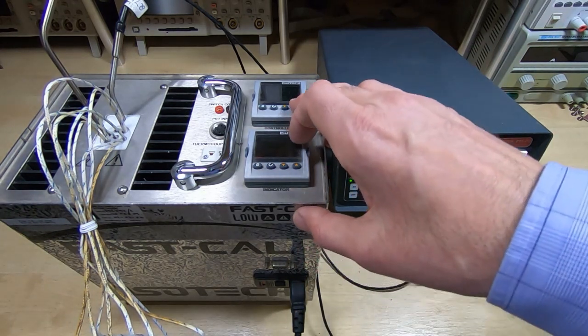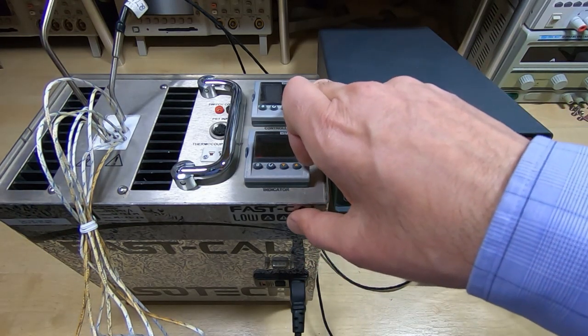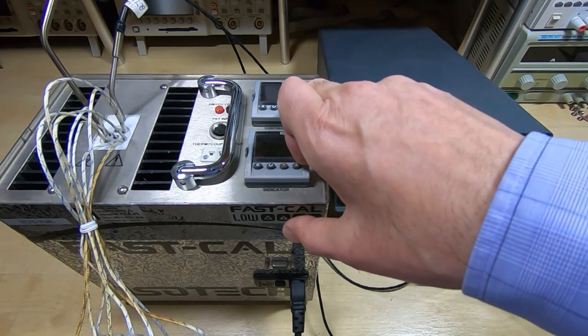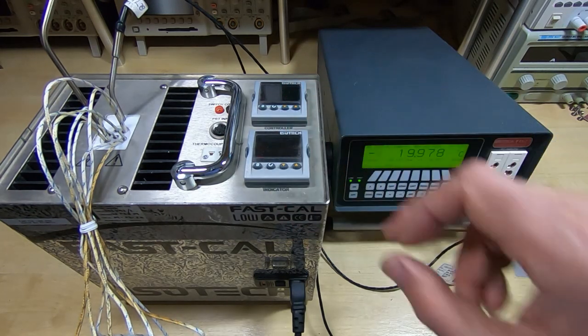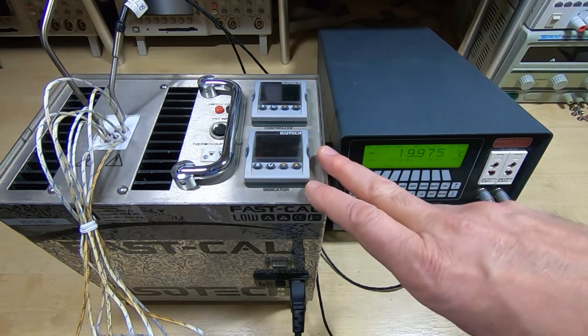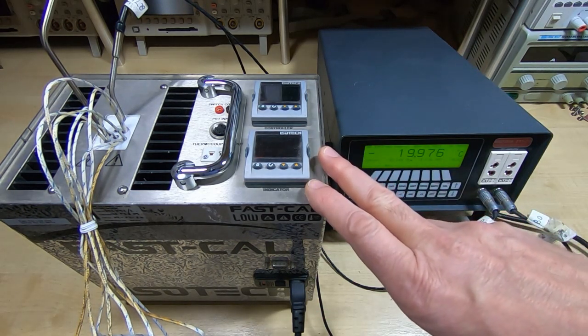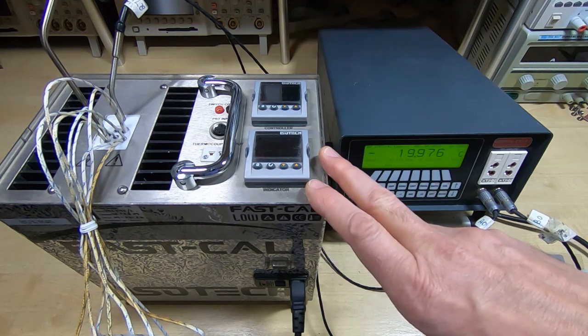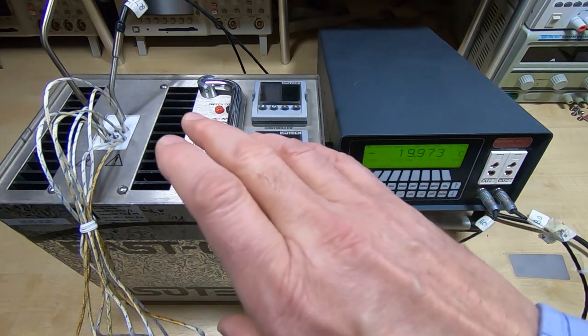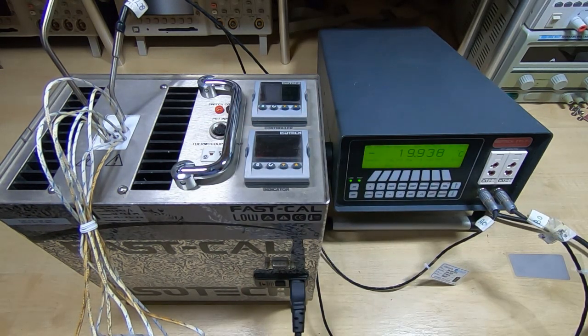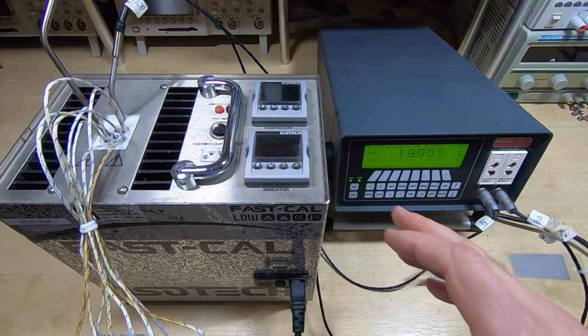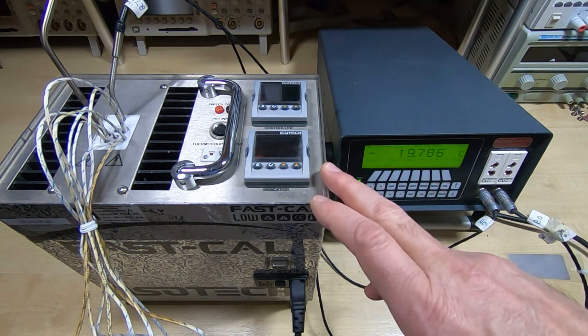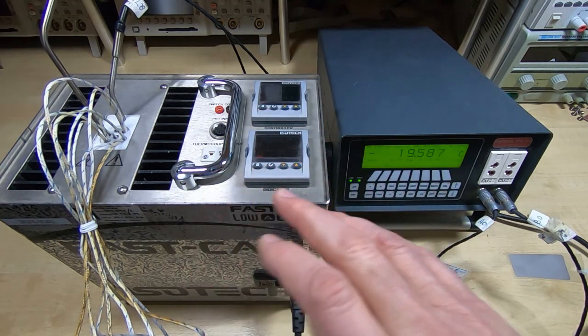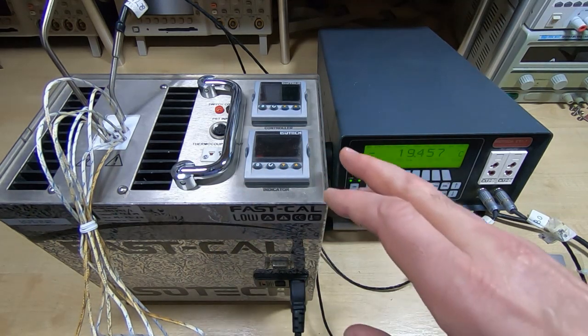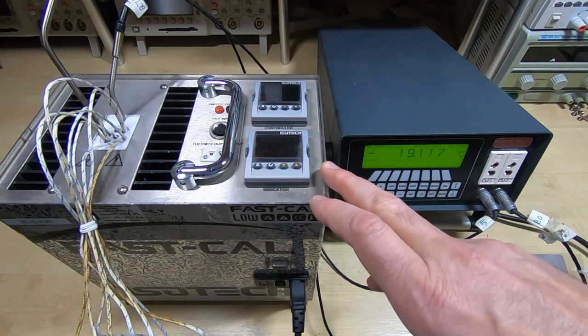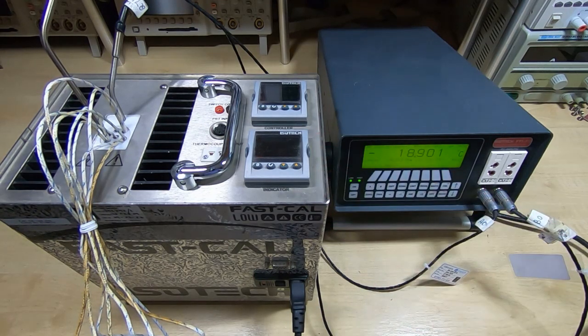So we change the calibrator value. I'll just adjust this. We'll go up now to plus 20. Okay, so this is now set to plus 20. We just now need to wait for it to ramp up to that temperature. Once it's had time to settle and everything's equalized, then we'll come back and we'll see what the readings are. The values we're looking at on the PC software capture are the uncorrected values, and I'll explain what I do with those once we've got all the values we want to measure.